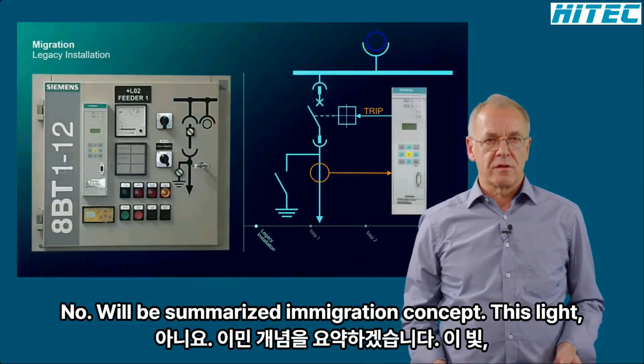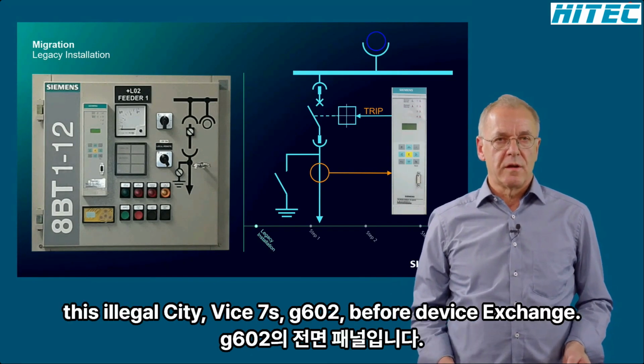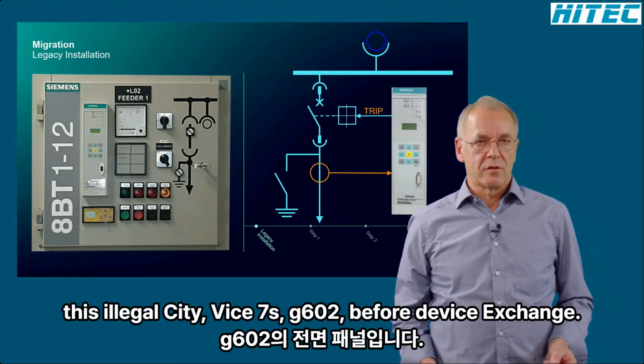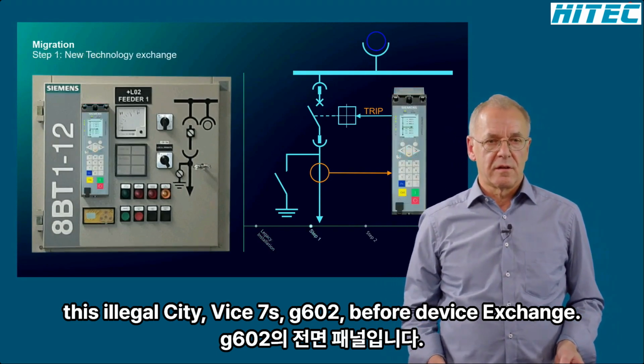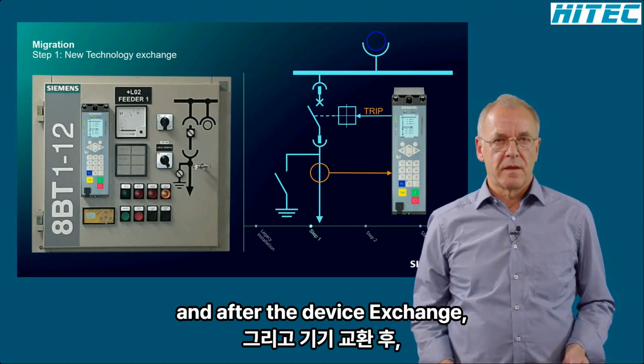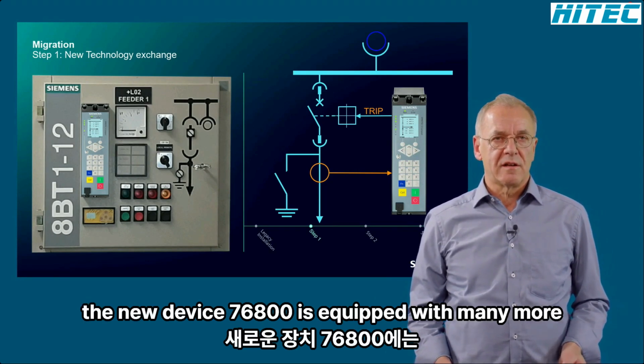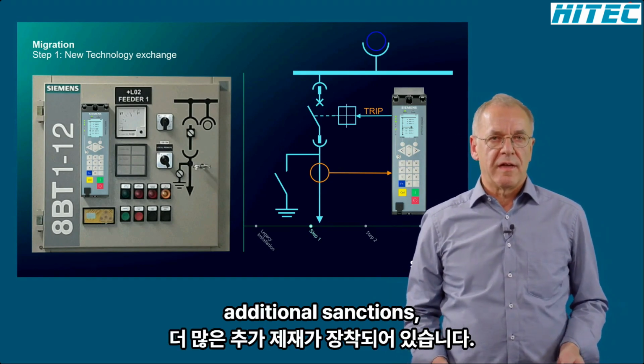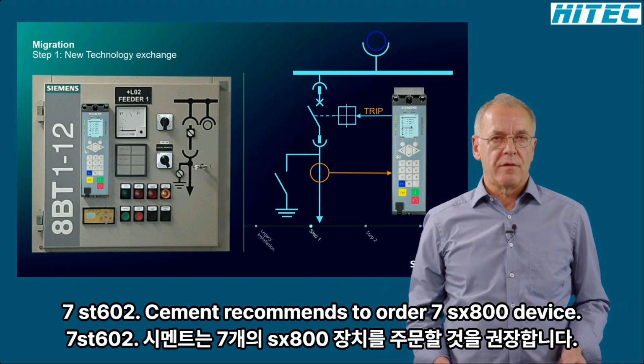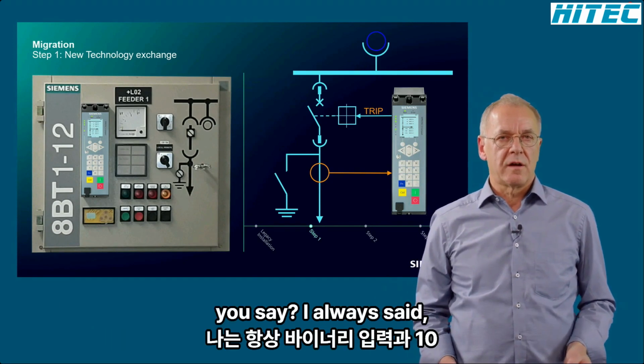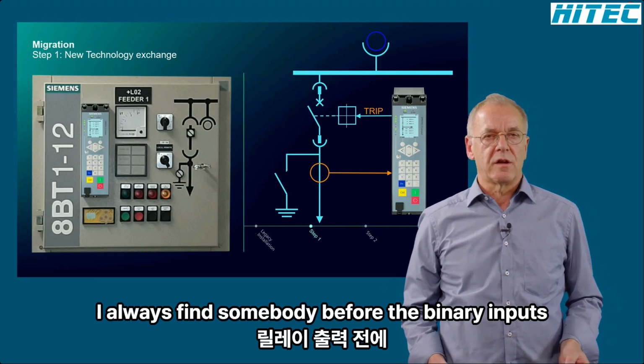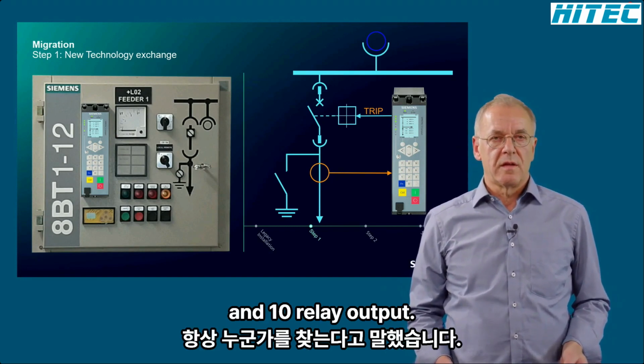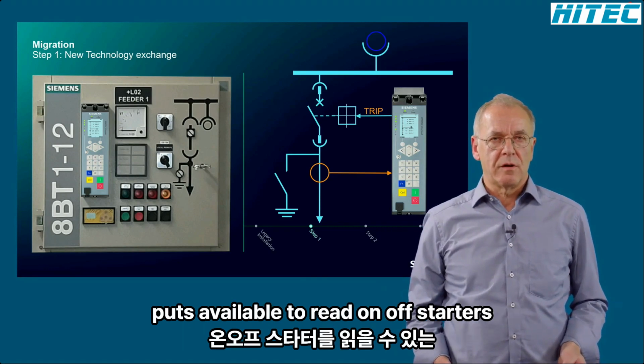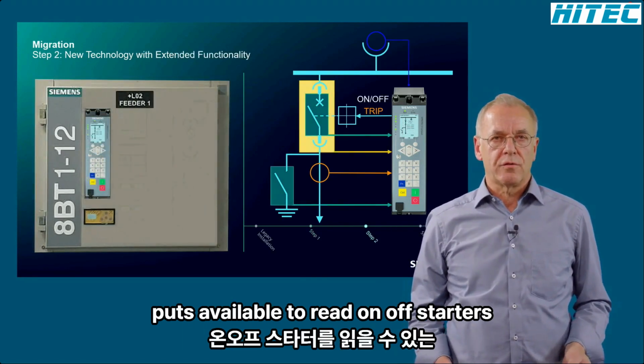Now, we will summarize the migration concept. In this slide, we see the front panel of the low voltage compartment with the legacy device 7SJ602 before device exchange and after the device exchange. The new device 7SX800 is equipped with many more additional functions than the 7SJ602. Therefore, Siemens recommends ordering the 7SX800 device variant with the I/O expansion module with 14 binary inputs and 10 relay outputs.